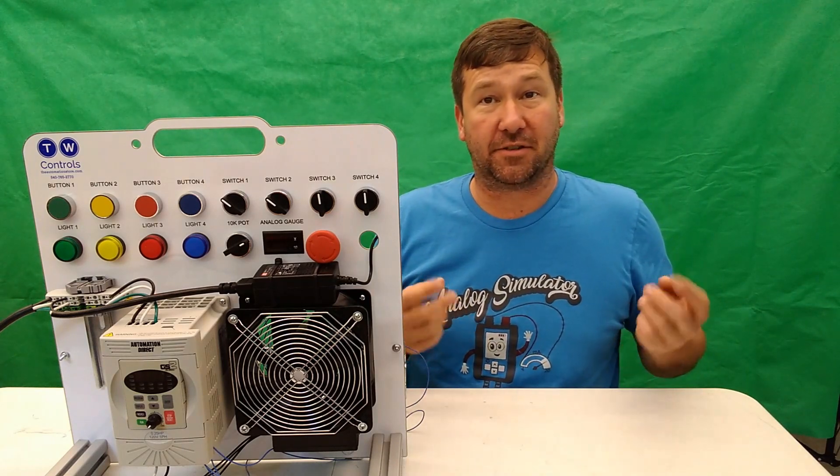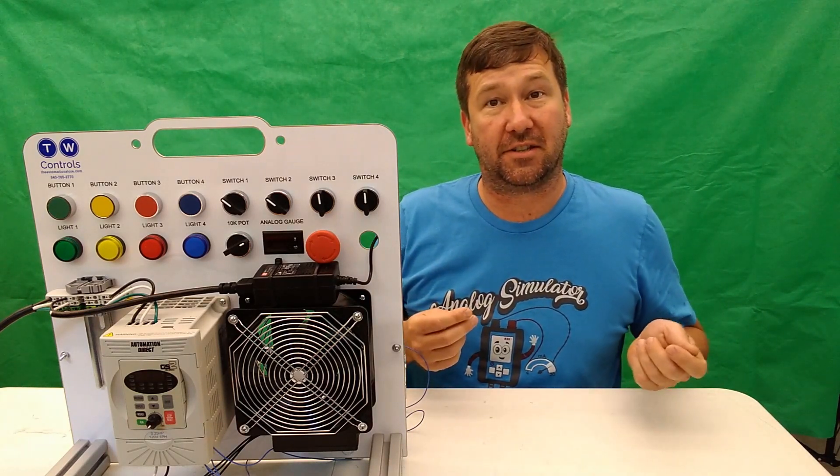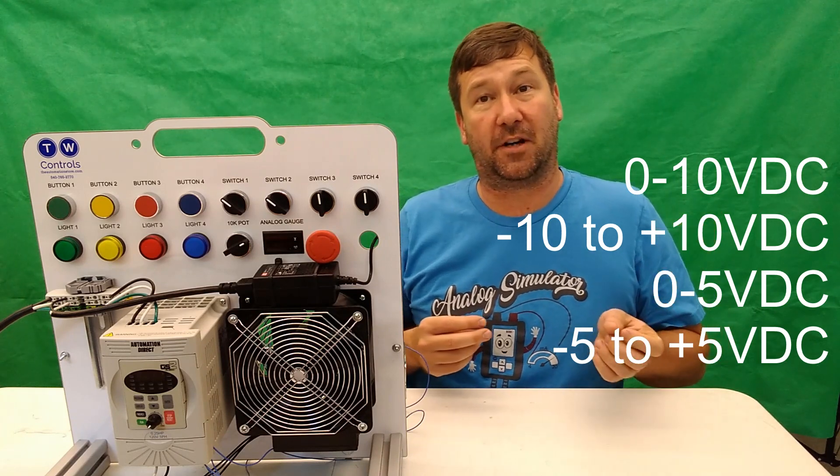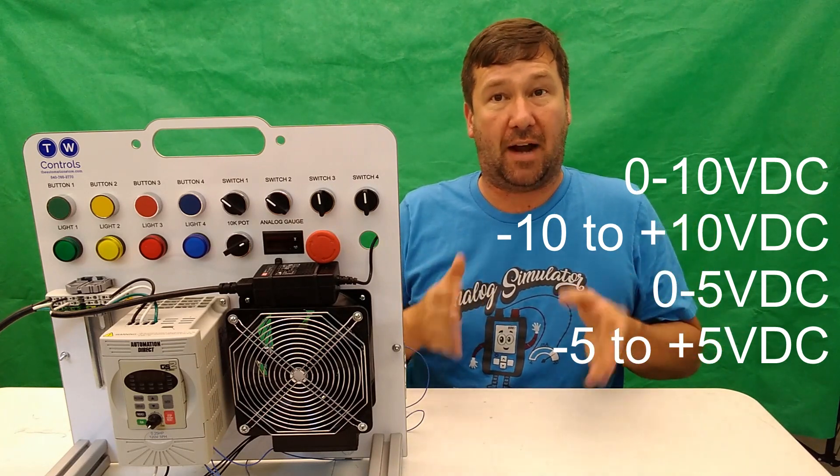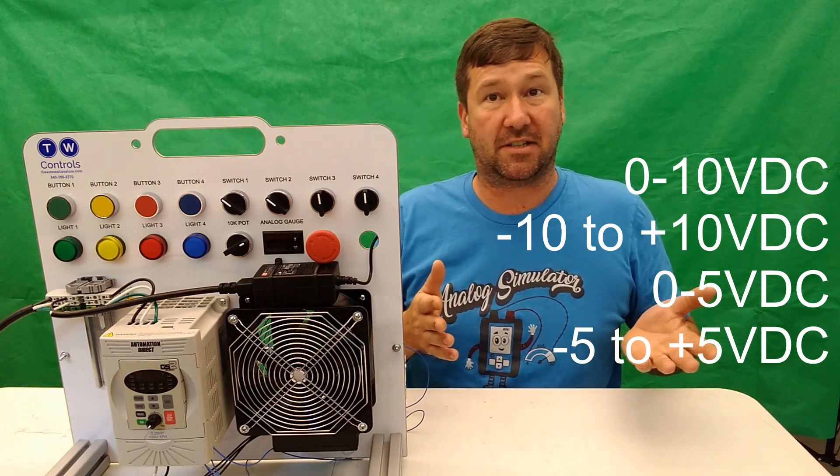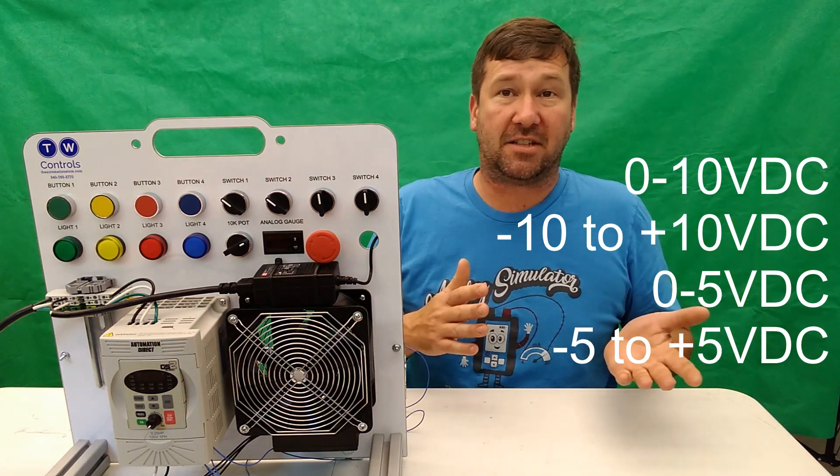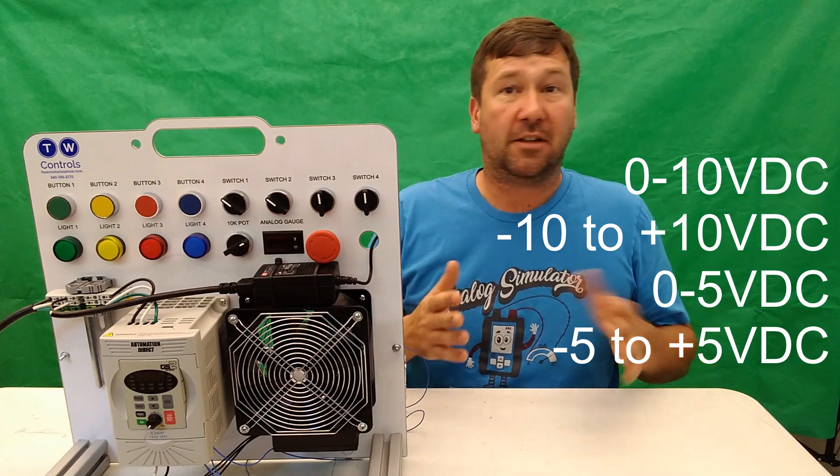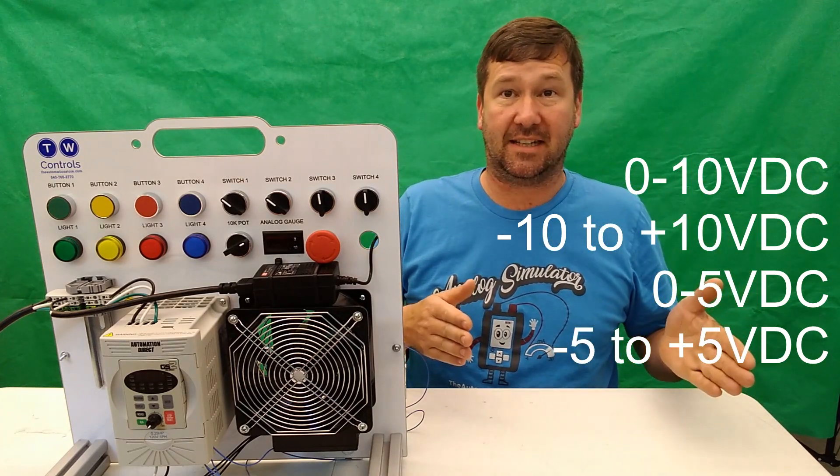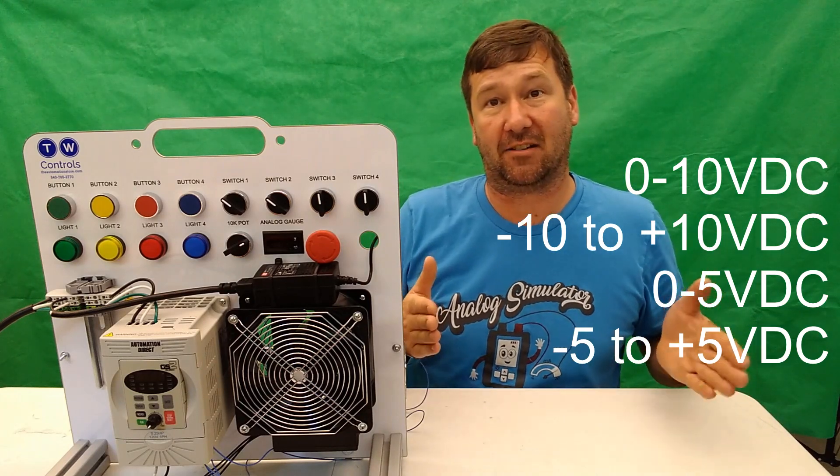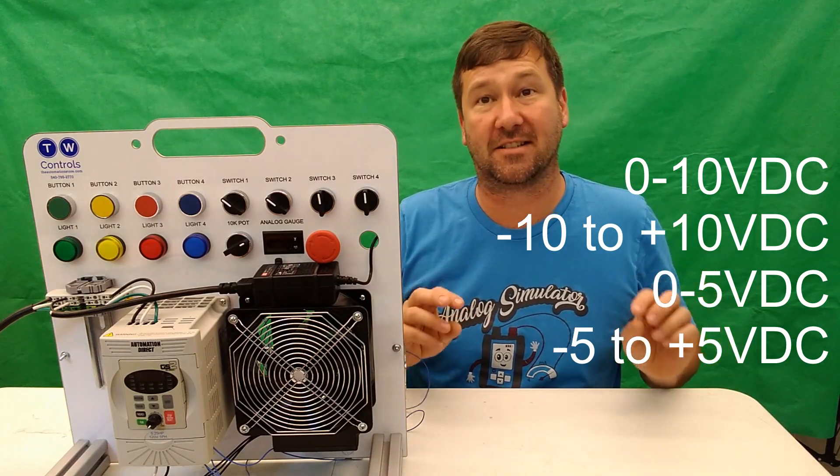Let's start with the voltage signal. Your typical analog voltage signal is going to be zero to 10 volts. You see a lot of this in drive applications where you're controlling drive speed. If you have an application that needs to go reverse, you'll typically see this signal reverse, making it a minus 10 to plus 10 analog signal, and this is used a lot in servo applications.